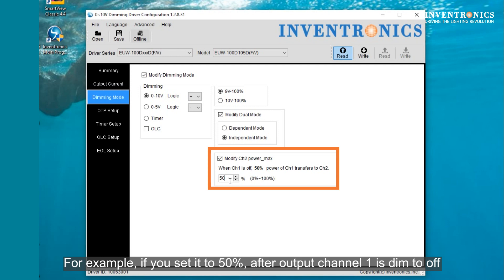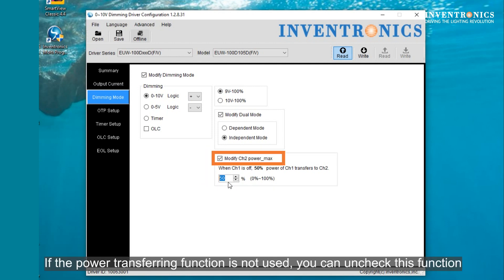For example, if you set this value to 50%, after output channel 1 is dimmed to off, 50% of the power of channel 1 will be transferred to channel 2. If the power transfer function is not used, you can uncheck this function.